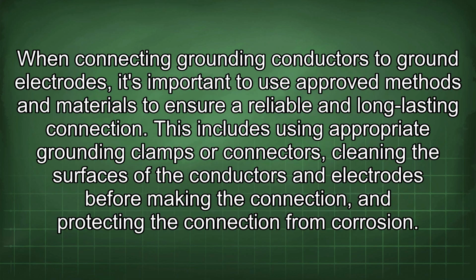When connecting grounding conductors to ground electrodes, it's important to use approved methods and materials to ensure a reliable and long-lasting connection. This includes using appropriate grounding clamps or connectors, cleaning the surfaces of the conductors and electrodes before making the connection, and protecting the connection from corrosion.